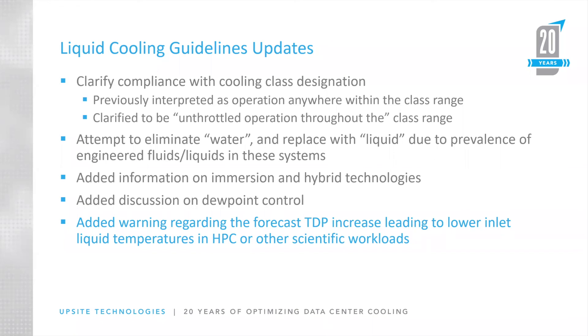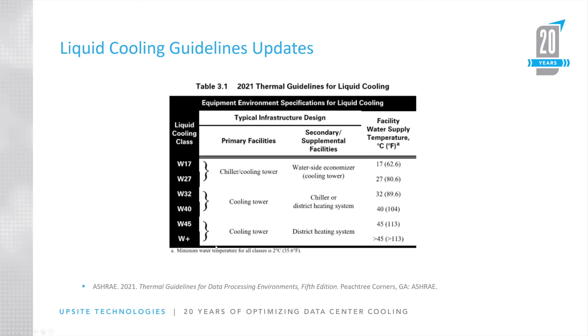For really high-density applications — 150 kW per rack or per tank and up — you're going to start seeing a need to lower inlet fluid temperatures. This is a big warning because if you're housing HPC equipment and running compressor-less cooling right now, that may work for a while, but it may change. We're seeing a trend from ITE manufacturers that those temperatures will start going back down, and some HPC facilities may need to add compressorized or evaporative cooling in place of pure dry cooling to bring inlet temperatures back down.